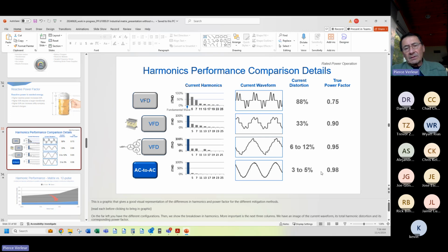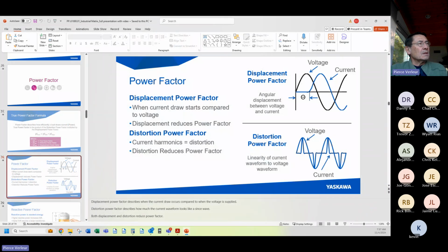You look at the older drives that they have in the plant, and they're running 0.75, I saw one at 0.67. So the change is huge when you go to matrix technology or active front end technology, as we proved at Whittier Narrows, the story I told you earlier. So this is distortion. So going back to the other presentation to explain power factor, displacement and distortion equal true.